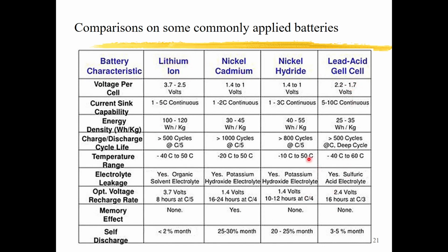For the comparisons here, you can quickly see that for the voltage per cell, the lithium ion is around 3.7 to 2.5 volts. And for the lead acid, the voltage level is about 2.2 to 1.7. And for the nickel series, nickel cadmium or nickel hydride, the voltage level is lower, 1.4 to only 1 volt. Okay, you can see the difference between the voltage levels and the current.